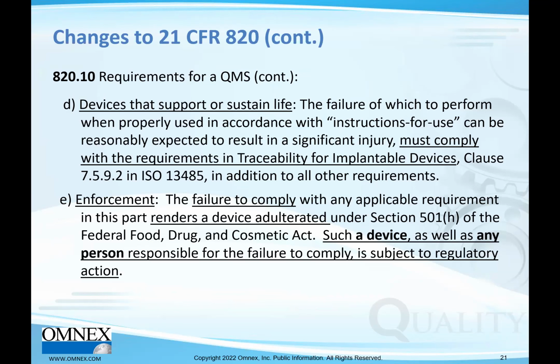Subparagraph E, enforcement. Failure to comply to this enforcement renders a device adulterated under section 501H of the Federal Register. Such a device, as well as any person. Now, you notice that I've made that bold. A device, as well as any person responsible for the failure to comply, is subject to regulatory actions. Regulatory actions could be statutory and punitive to the device or the persons. And by the way, to remind everybody, once this is published, it becomes law, and it's not voluntary like 13485 is.